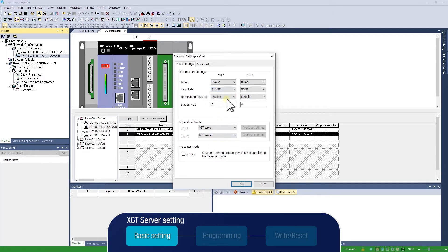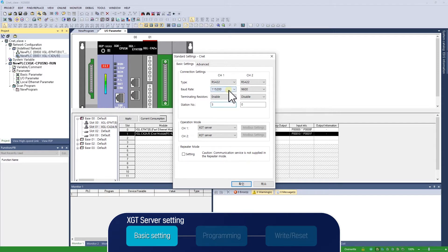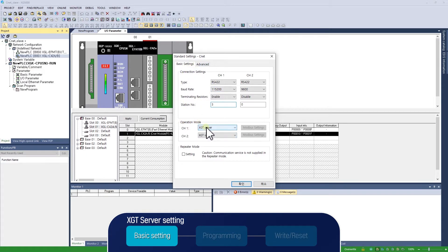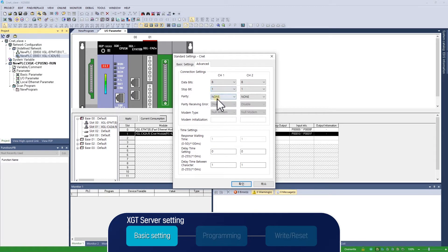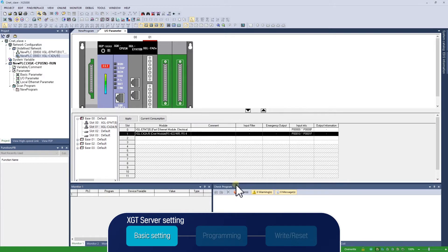Next, we will activate the terminating resistors on both PLCs and set the station number to 3. Operation mode should be set to XGT server. We will move on to the Advanced Settings tab. Set data bit to 8 bit, stop bit to 1 bit, and parity bit to none. And then the communication setting is finished.